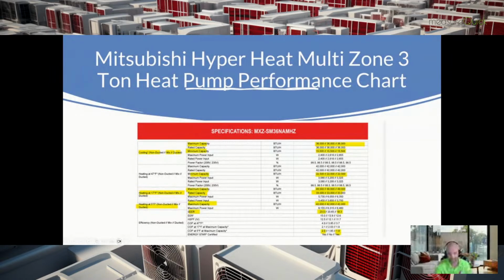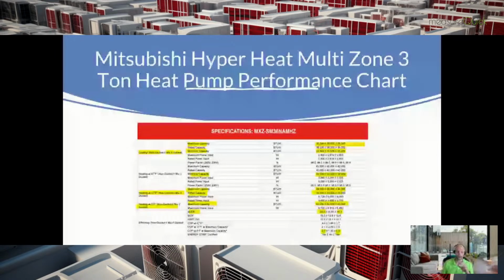You've got your maximum capacity. It's a 3-ton heat pump. And then notice this, you have a minimum capacity of 15,000 BTUs. That's almost a ton and a half of cooling capacity that you're getting down to, but it's only a ton and a half. So think about if you have a 9,000 BTU head coming off this somewhere, a 6,000 BTU head somewhere, and a 12,000 BTU head somewhere. Depending on what's calling for cooling at what time, you may be running that 6,000 BTU head and only ever getting 6,000 BTUs out of it, nothing lower. Or you may be running that 12,000. Think about that, a whole ton of cooling you're running at all times.